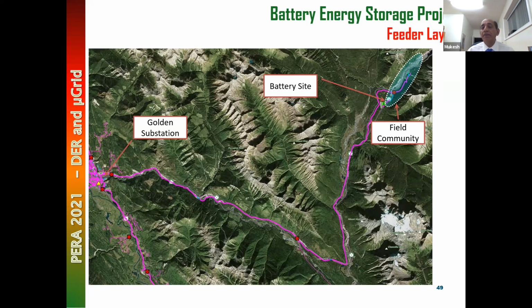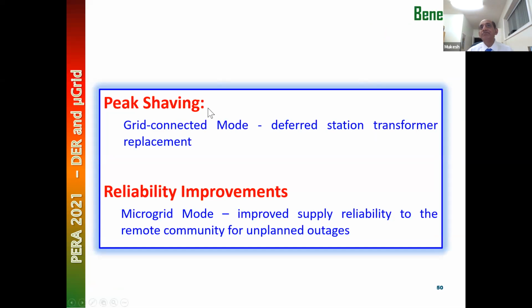So here is what we decided. We are going to put in a 1 megawatt battery. Sorry, not 1 megawatt, a 1.25 MVA battery, right next to this community. It did two things, two benefits. It shaved the peak. When there's a peak load and the transformer was just approaching its limit, we got 1 megawatt of supply from the battery for the peak hour. So the battery shaved the peak by 1 megawatt, 1 MVA. And then it gave a reliability improvement. When we lost the feeder, the battery, which I'm going to show you in a minute, could supply our load in a microgrid.